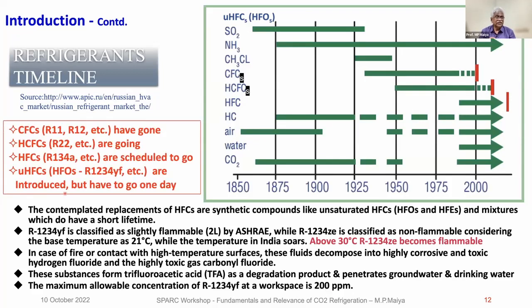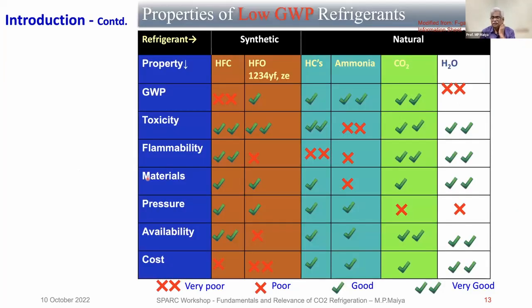So you can see CFCs have gone. HCFCs are going, still going. HFCs are scheduled to go, at least phase down. And unsaturated HFCs, that is HFOs like 1234yf, are introduced now as a replacement, but they have to go one day. Coming to comparing the properties of refrigerants, you can see water. These are natural refrigerants, these are synthetic. You can see, all are not good.